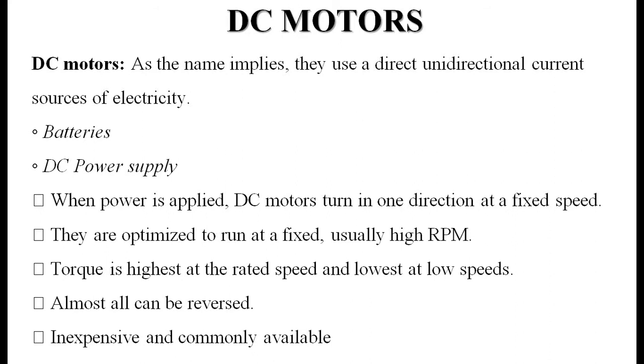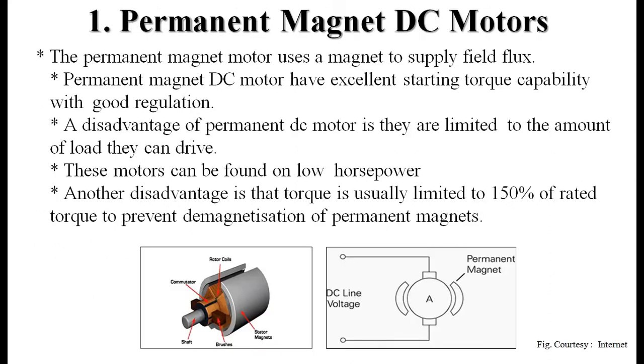The first type is PMDC — the Permanent Magnet DC motor. The permanent magnet motor uses a magnet to supply field flux. PMDC motors have excellent starting torque capability with good speed regulation. A disadvantage is they are limited in the amount of load they can drive; these motors are found in low horsepower applications. Additionally, torque is usually limited to 150% of rated torque to prevent demagnetization of the permanent magnets.